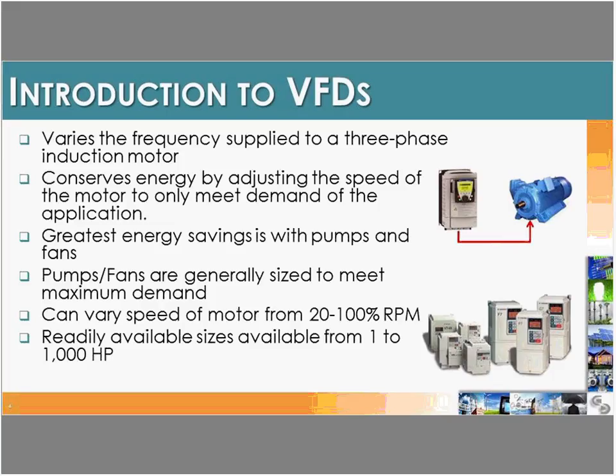When we adjust the speeds of motors, we're generally looking at 20 to 100% speed of what VFDs can control to. They can actually go from zero all the way over 100% RPM — I've had some applications where we may have to overspeed that motor, and some VFDs can be programmed to do that. VFDs have been available on the market for many years, and manufacturers have readily available sizes from 1 to 1,000 horsepower, with custom-made designs available for even larger applications.